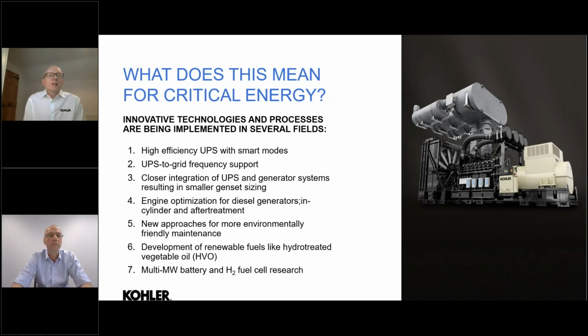So what does this mean for critical energy? Well, of course, we're looking at innovative new technologies, and they're being implemented in several fields. High efficiency UPS with things such as smart modes. UPS can be used, of course, for grid support and frequency support for the grid. A closer integration of the UPS and generator systems can result in smaller generator sizing. Of course, engine optimization for diesel generators with improved in-cylinder technology and after treatment.